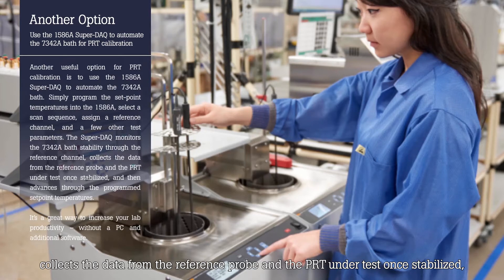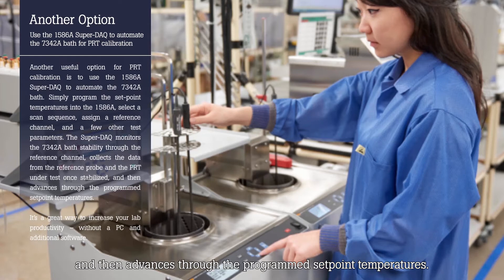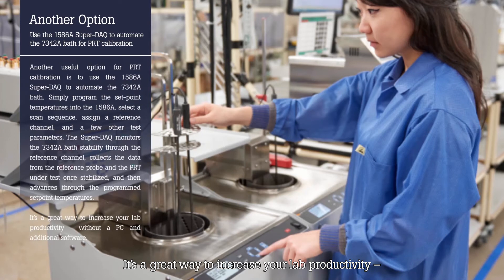The Super-DAQ monitors the 7342A bath stability through the reference channel, collects the data from the reference probe and the PRT under test once stabilized, and then advances through the program set point temperatures. It's a great way to increase your lab productivity without a PC and additional software.